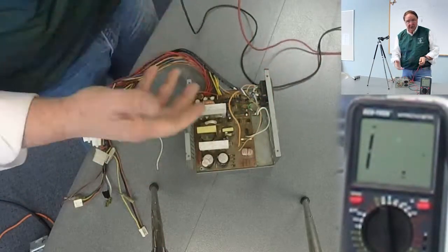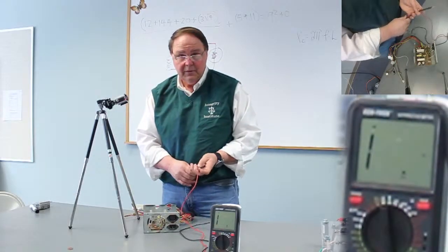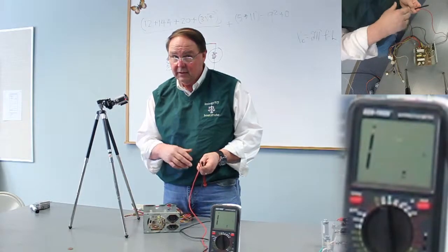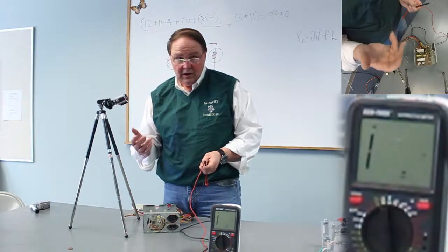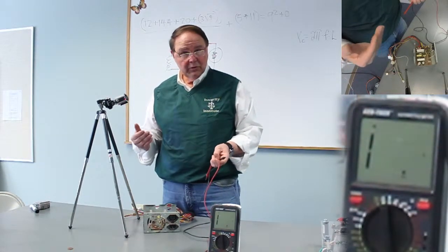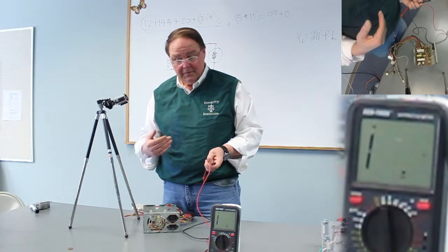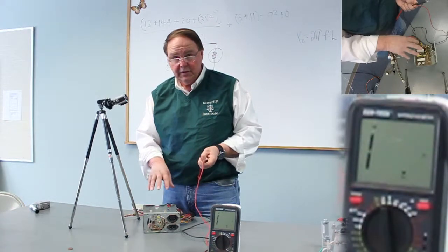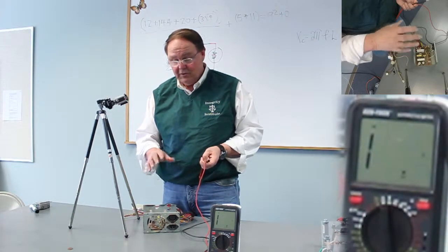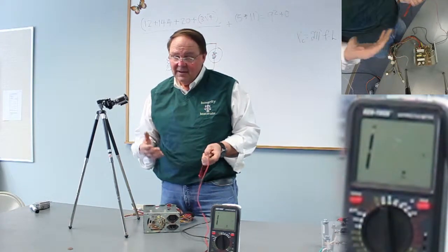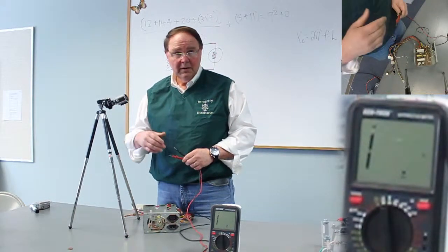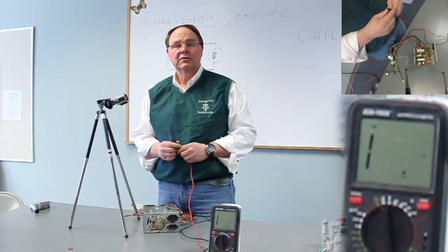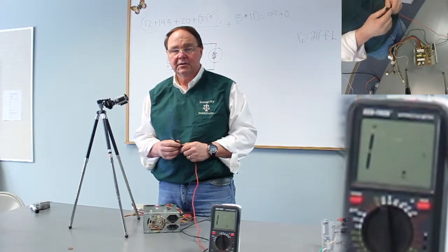Therefore, if you get objectionable current through this equipment ground because somebody has improperly grounded the equipment ground into neutral, which really all it does is become a parallel neutral because the neutral is a current carrying conductor, you're going to subject this printed circuit board to objectionable currents that it was never intended to handle. Of course, then you start winding up replacing printed circuit boards, ICs, etc.